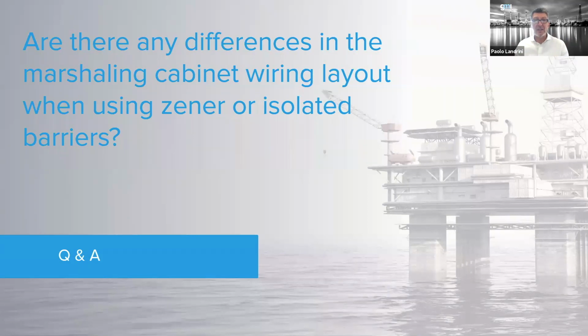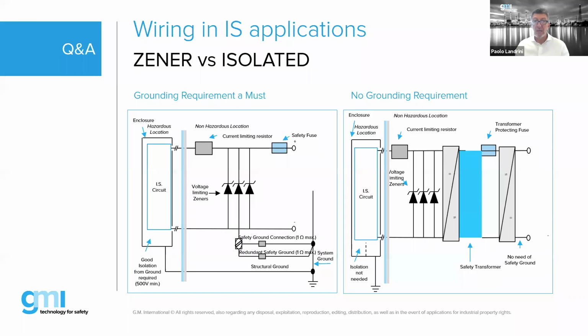Next, are there any differences in the wiring between an isolator and a Zener barrier? Well, basically, the wiring, can I answer, Paolo? There is no difference. As you said, the main difference in this case is that the field device needs the isolation from ground, 500 volt, and an earth connection for the Zener barrier. That is the most important difference. But in terms of connection between the control system and the sensor and the barriers, nothing changed.